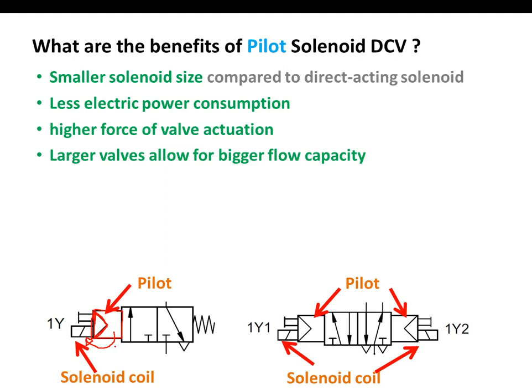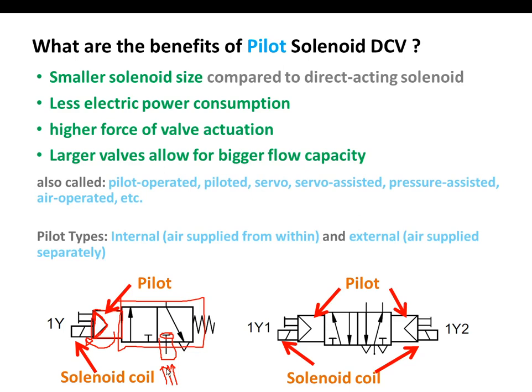With higher actuation forces, we can have bigger valves that allow for larger flow capacity — allowing more pressure to flow at the same time. This pilot could also be called pilot operated, piloted, servo, or servo assisted. It can be either internal — where pressure is taken from inside the valve — or external, where pressure is taken from an external circuit.